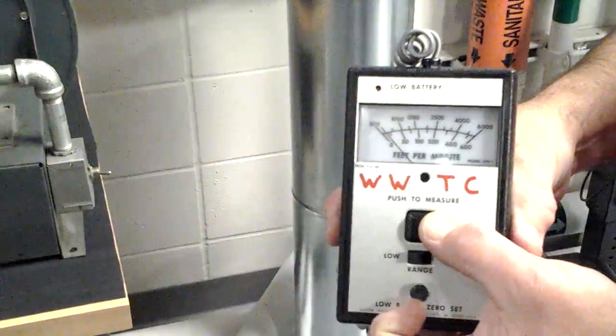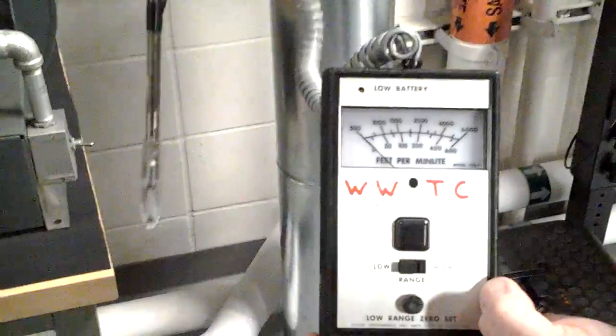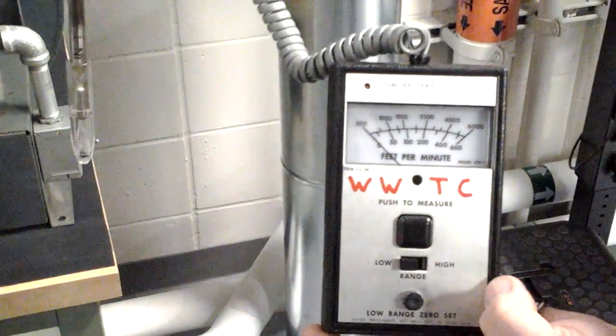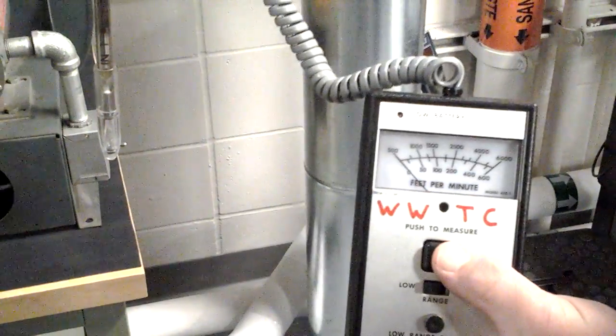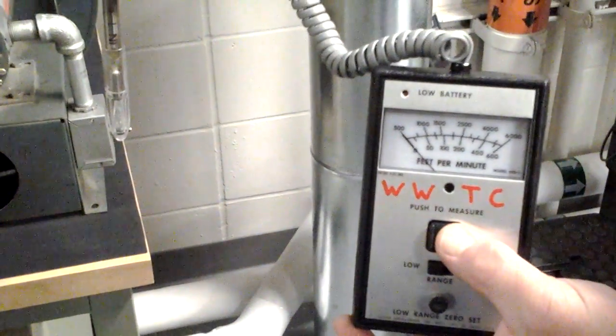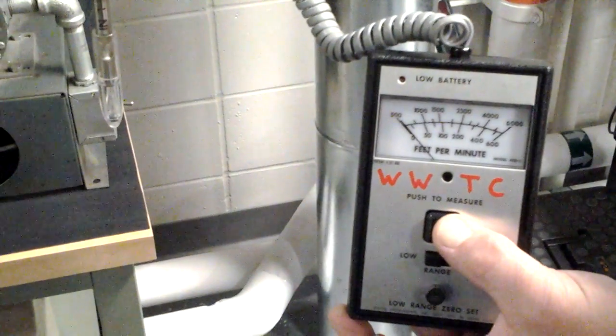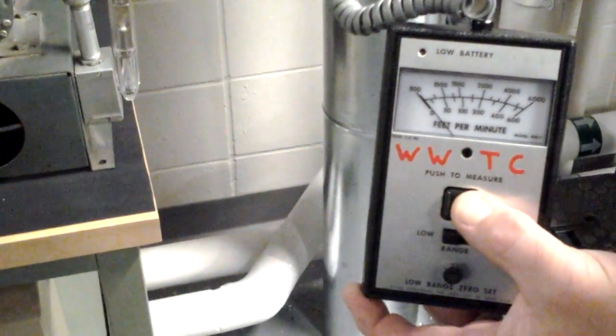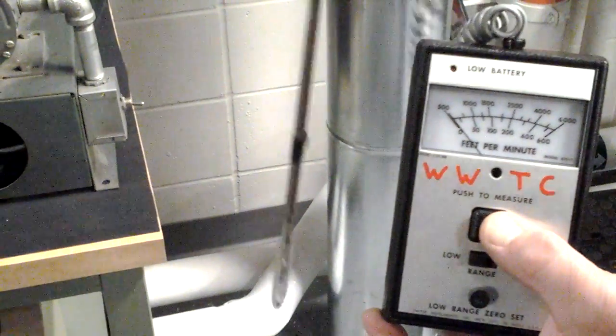Set the range switch to low. With the probe tip cover in place, depress the push to measure switch. After a momentary warm-up period, the meter will react to the low-range zero-set control knob. Adjust to position the pointer at 0 feet per minute. Release the switch.